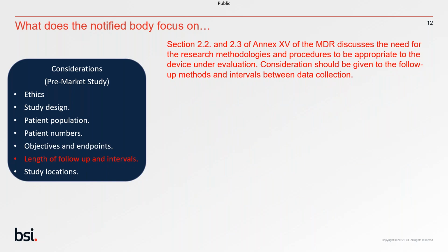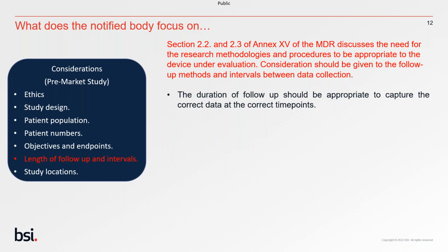Length of follow-up and intervals. Sections 2.2 and 2.3 of Annex 15 discuss the need for the research methodologies and procedures to be appropriate to the device under evaluation, and specifically say consideration should be given to the follow-up methods and intervals between data collection. So make sure that your data collection points are appropriate, and the duration of the follow-up is appropriate to the device to make sure that it captures the correct data at the correct time points.